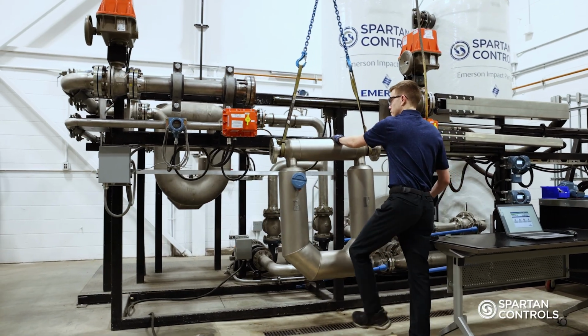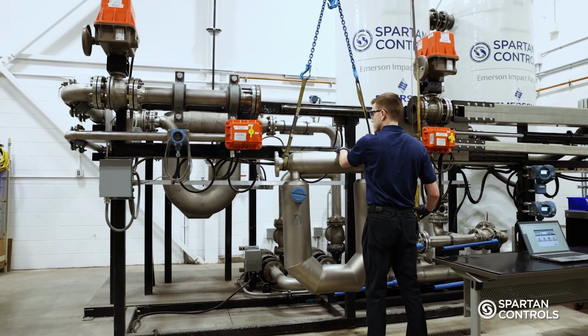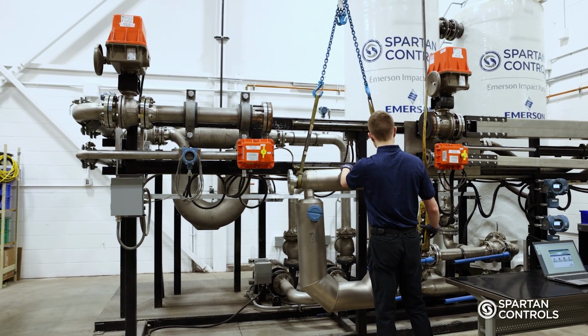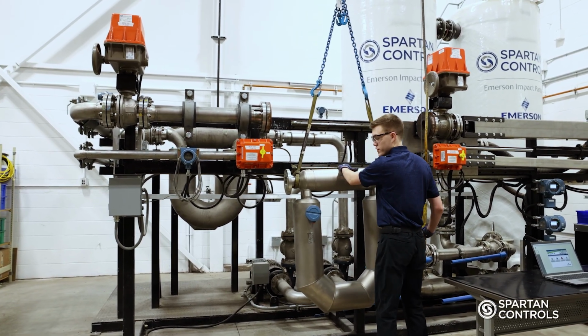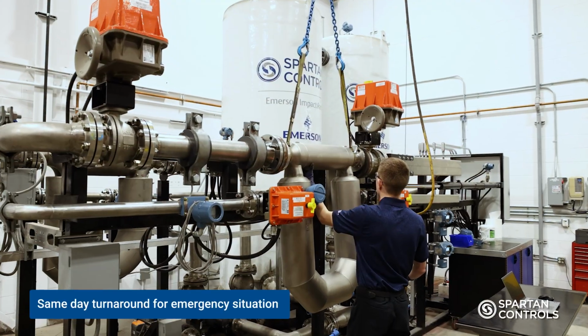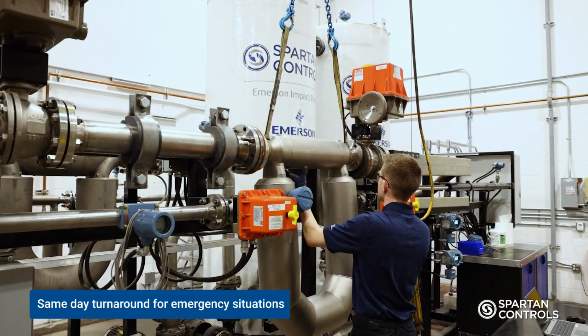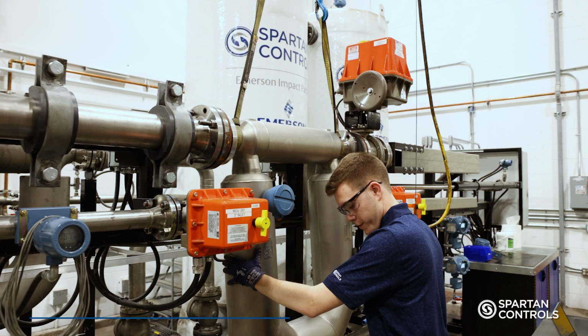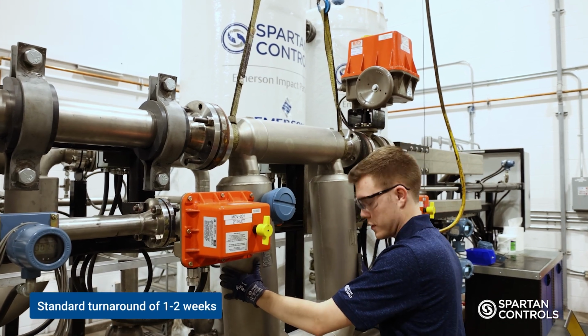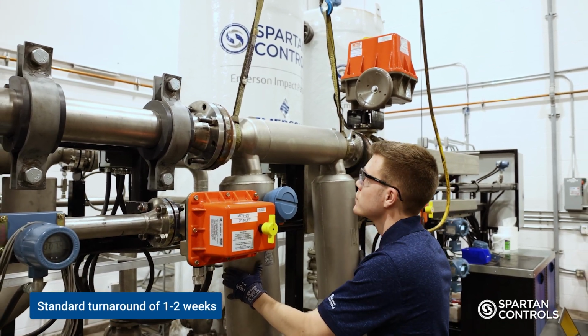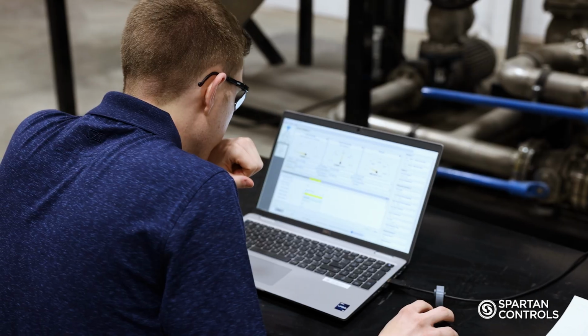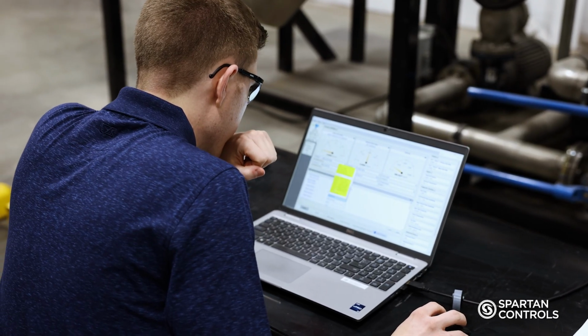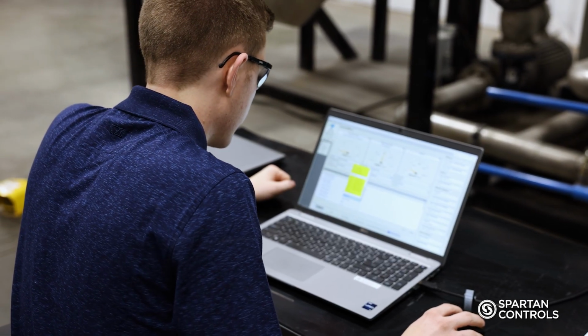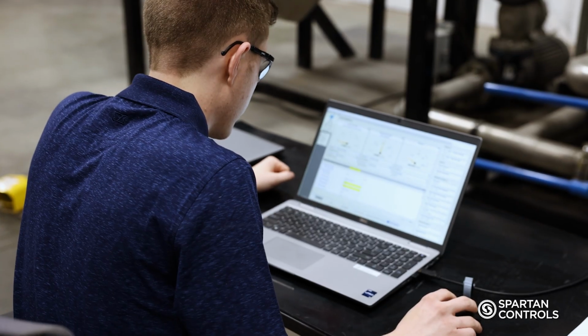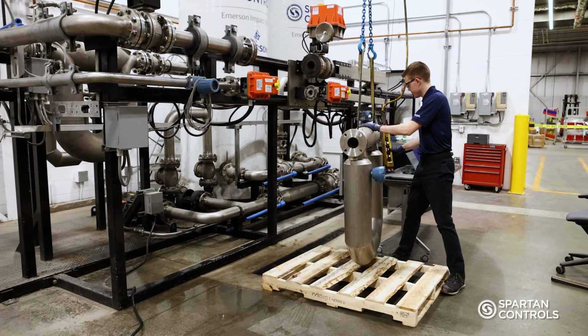Utilizing our hydraulic ram mechanism allows for quick and boltless installations of test meters, enabling us to offer same-day turnaround capabilities for emergency situations, with standard turnaround times of 1 to 2 weeks on meters that are provided to us pre-cleaned. Whether you require annual proving for regulatory purposes, repair, testing, or accuracy verification where a meter's performance is in question, our experienced, factory-trained and certified technicians will ensure all your needs are met.